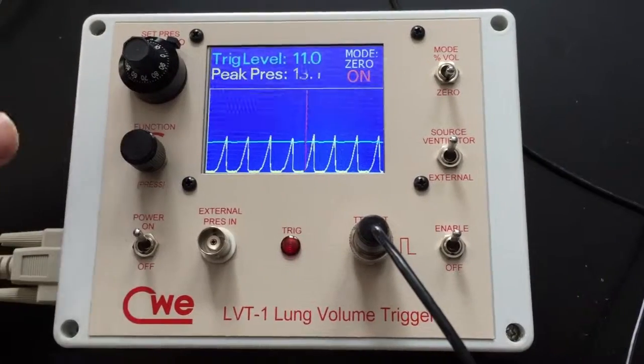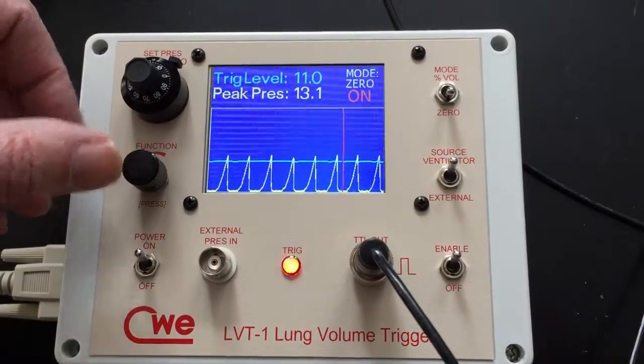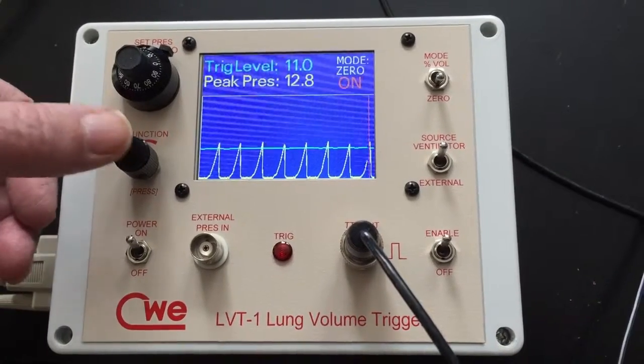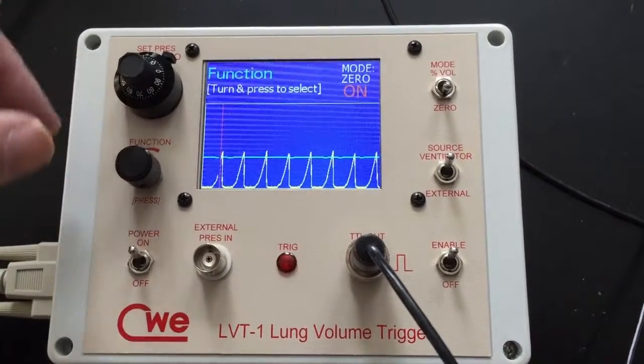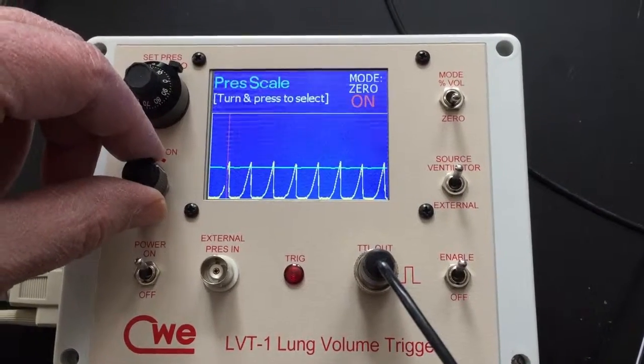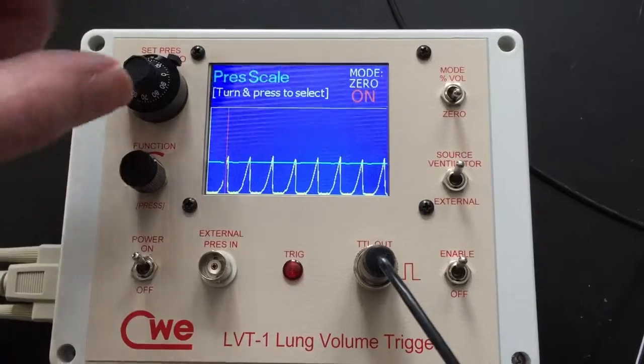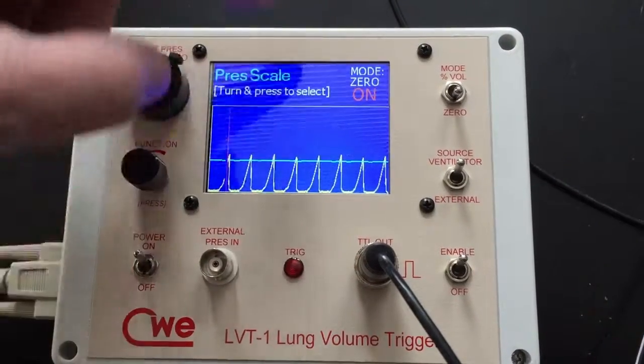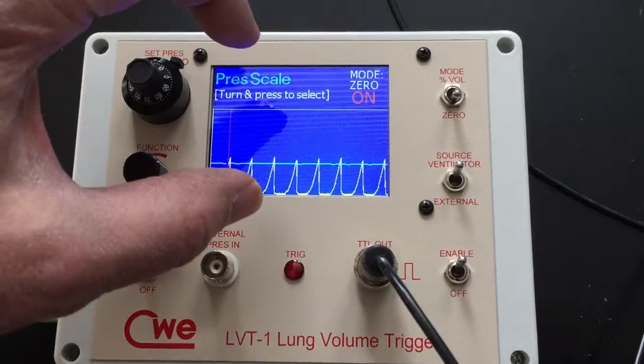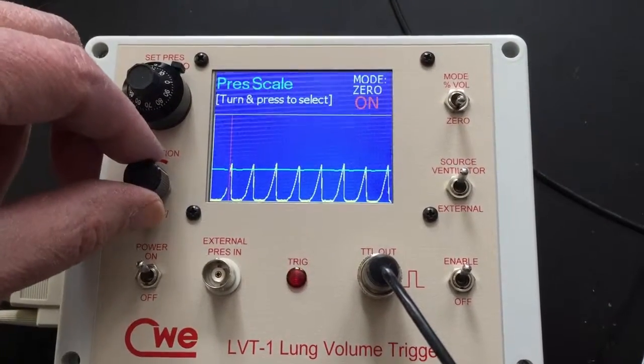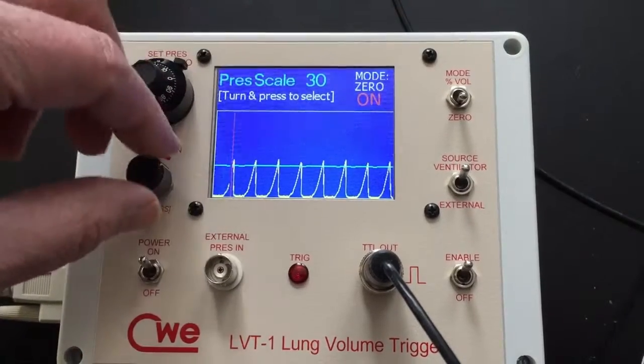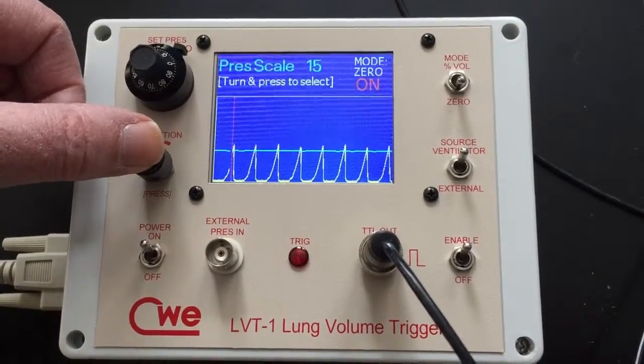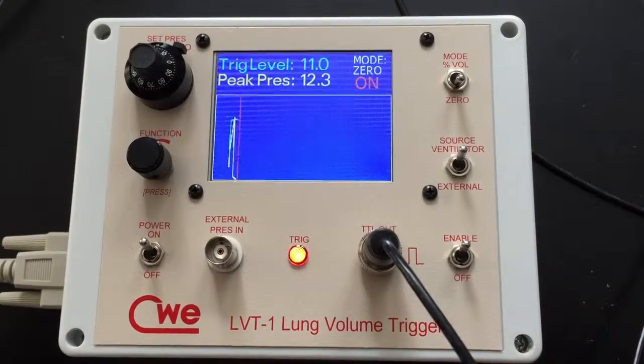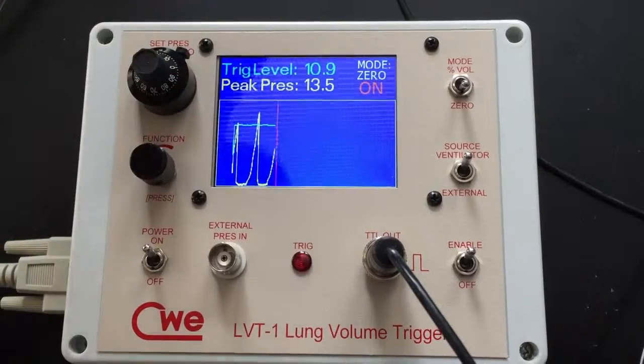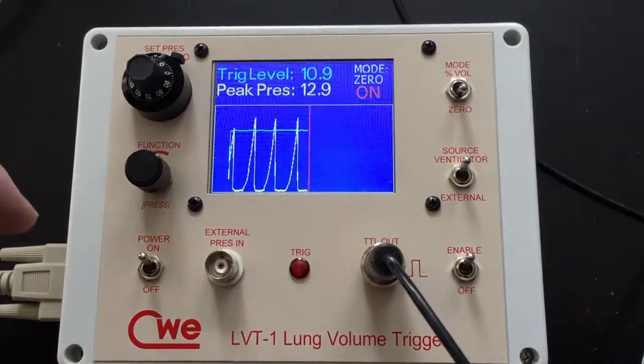Okay, now I'll just illustrate some of the internal functions and setup, which you really only have to do probably one time or as needed. So if you just press the function button, it moves you to this menu, and then you turn it to select the function you want to change. So this is pressure scaling, which on this graph is the scaling in centimeters of water for full scale. So if we select that, it's now at 30 centimeters. I'll halve that to 15, press the button, and it'll return. And now you can see you've enlarged the sensitivity of the screen.